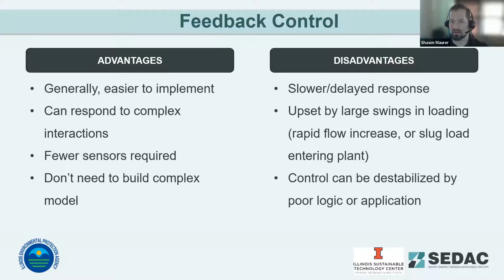We've seen in some plants where the DO never really settles at a set point. It's bouncing back and forth, 1.5 milligrams per liter. Ideally, with an optimal control, that should settle at your set point, with less than 0.5 milligram per liter adjustment, unless you've got a really large upset coming into the plant.